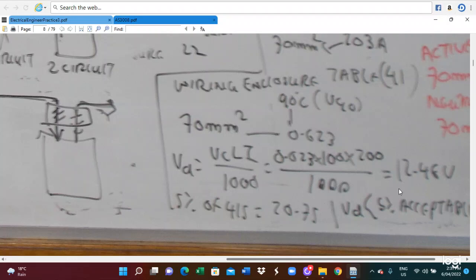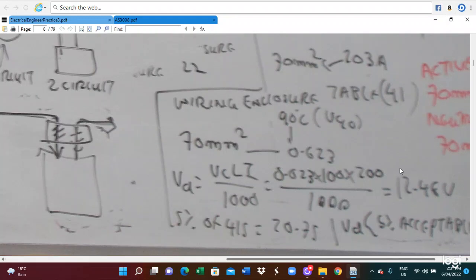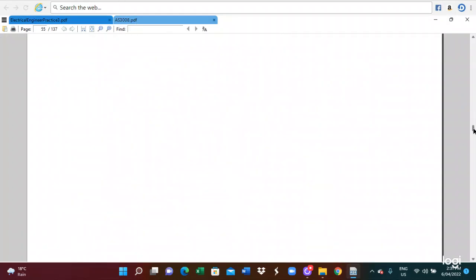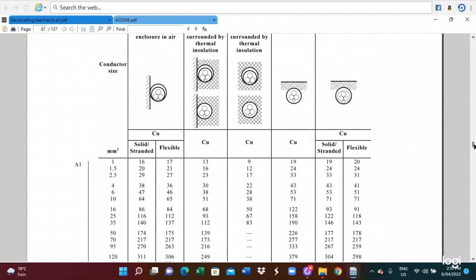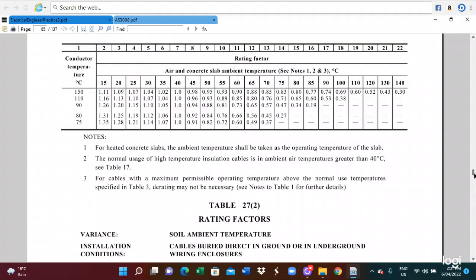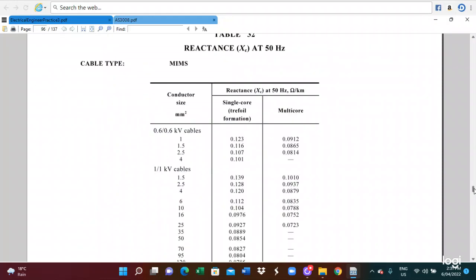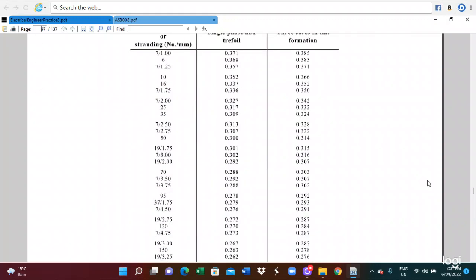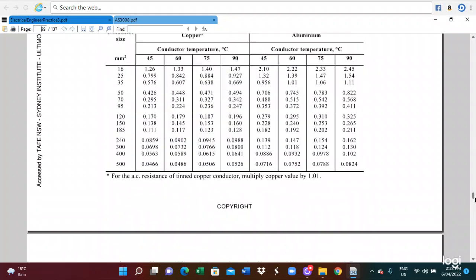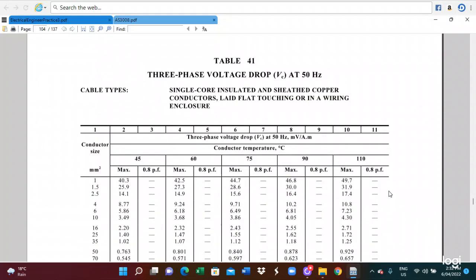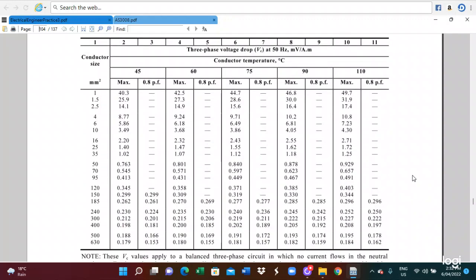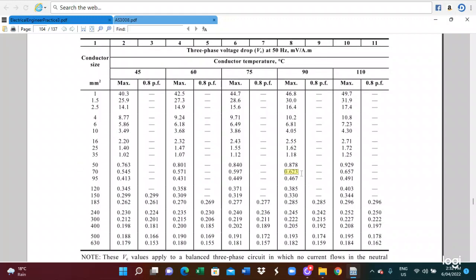And then we have to find the VC. We find the VC from table 41. From table 41, the VC value for 70 millimeter square at 90 centigrade is 0.623. Because it is single core cable, we refer to table 41 to calculate the VC value. For the voltage drop calculation we utilize table 41, the three-phase voltage drop. For 90 degrees centigrade and 70 millimeter square, you get 0.623. This is the VC value.